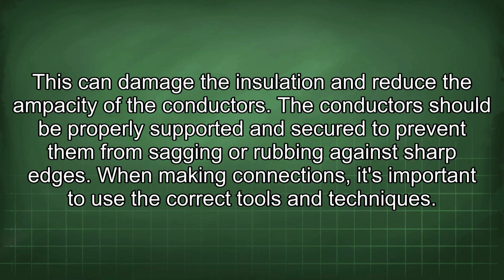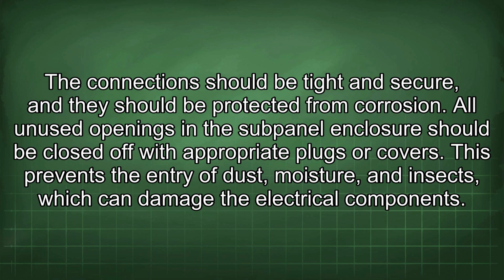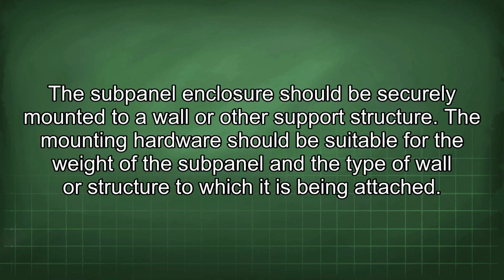When making connections, it's important to use the correct tools and techniques. The connections should be tight and secure, and they should be protected from corrosion. All unused openings in a subpanel enclosure should be closed off with appropriate plugs or covers. This prevents the entry of dust, moisture, and insects, which can damage the electrical components. The subpanel enclosure should be securely mounted to a wall or other support structure. The mounting hardware should be suitable for the weight of the subpanel and the type of wall or structure to which it is being attached.